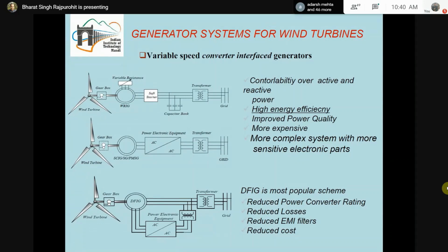So these schemes are able to work in a variable speed mode, able to generate more power from the same site, and able to meet the grid connection requirement by utilizing this power electronic equipment. Now please see the third scheme. The third scheme, the bottom figure on the left hand side, is known as the doubly fed induction generator. This is also a wound rotor induction generator, but the name doubly fed is there because in this case the rotor and the stator of the induction generator are connected to the grid, and power can be supplied into the machine or taken out of the machine. Because this machine can be fed from two sides, one from the stator and one from the rotor, that is why it is called the doubly fed induction generator.